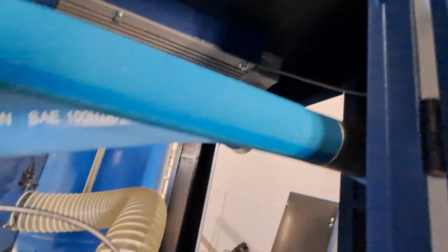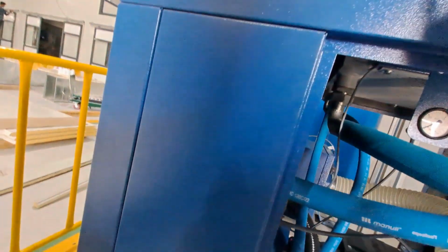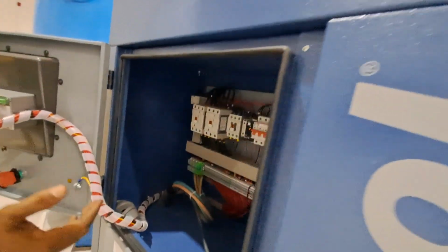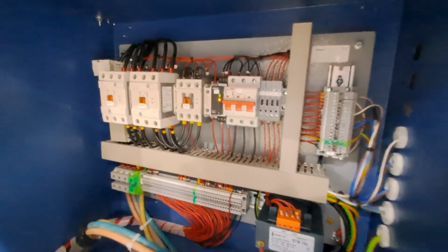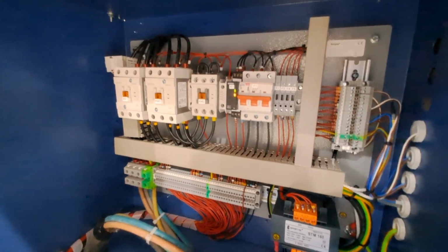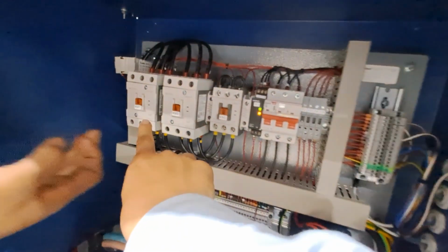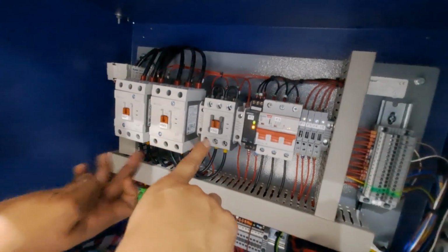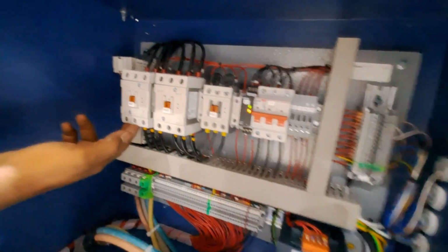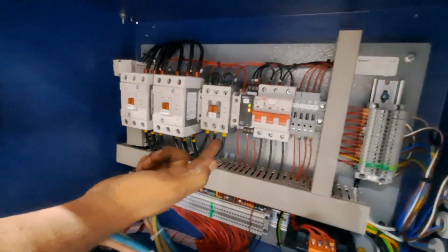Okay, so let us go to the controller and explain to you the control system. It's a star delta panel. The motor is working with the star delta connection here. So these three contactors, KM1, KM3 and KM2. This is the line contactor. This one is delta. This one is star.